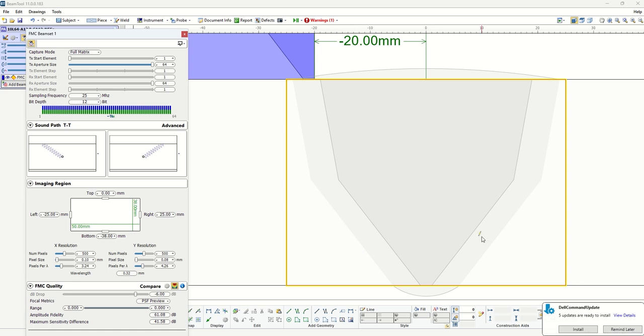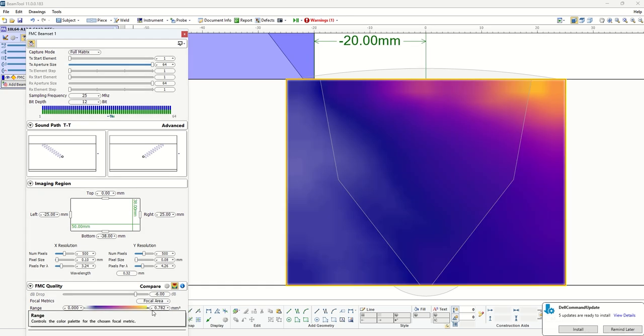Obviously, if we move to the upper side, as expected, now our point spread function will be spread out and low amplitude, but on this side, it seems like it is good. Then we can look into our actual focal area as another metric. Again, the focal area shows us how tightly focused our beam is here, and we want to get as small a focal area as we can.